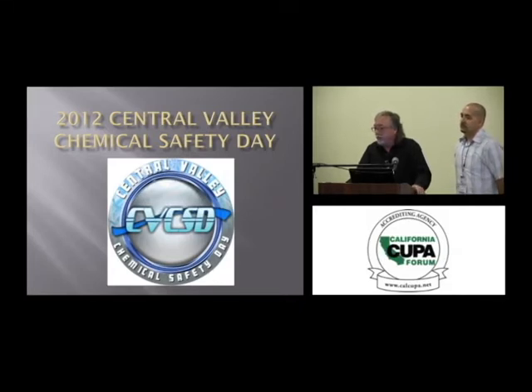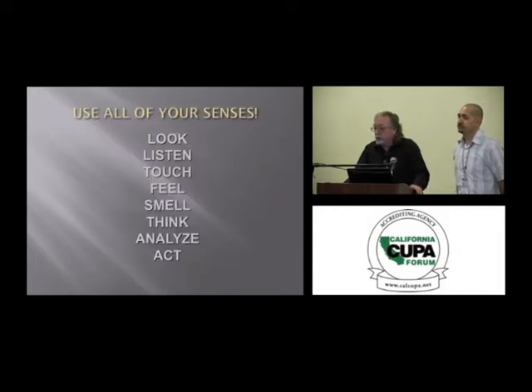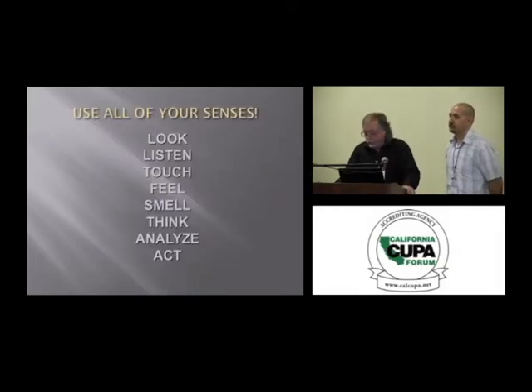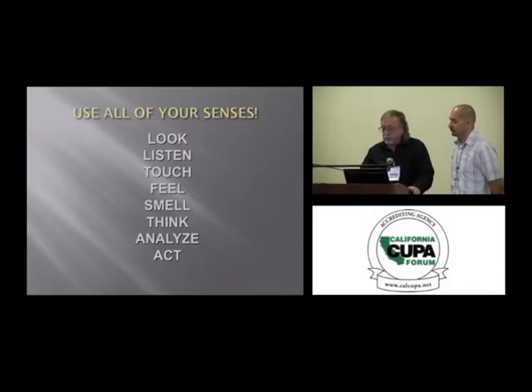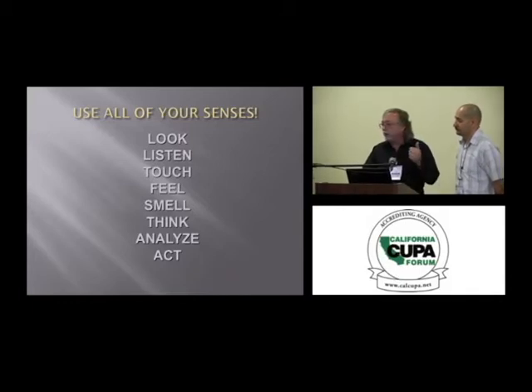So these guidelines would be applicable to those systems? I would say levels and pressures at least. Levels and pressure? Yes. Yeah, and the visual walkthrough, noise, vibration, etc. Yeah, very good. Yeah, bottom line is runtime hours, levels, pressures, temperatures, all important information. The daily rounds aren't just to catch something today. They're also to look at trending, slow changes.